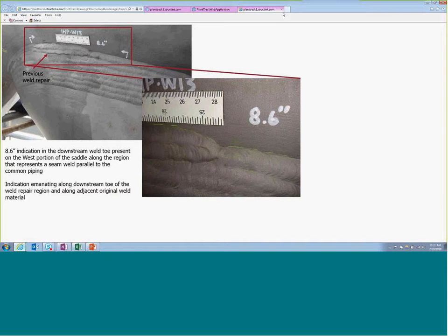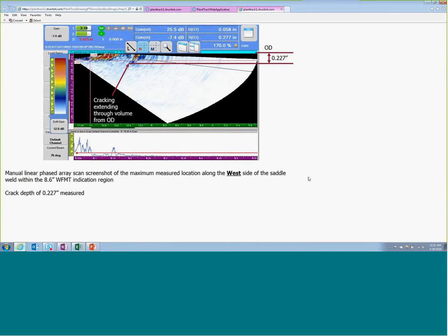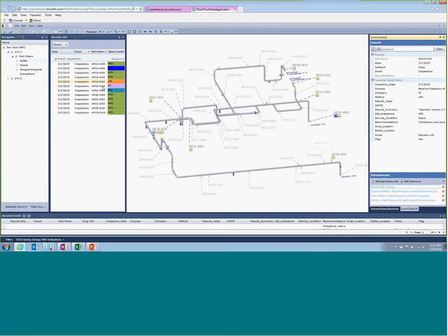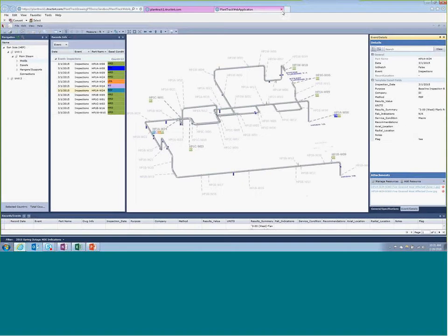So again, this mag particle. If I go back and say, all right, show array, same concept. With information, you can start to see that some of that was captured from that particular method. And I also want to show the replication as kind of the final deal as well. So hopefully it's loading, we're not getting any lag, but this is creep cavitation in grade 91, and this right here is bad, very bad. So this is all captured.